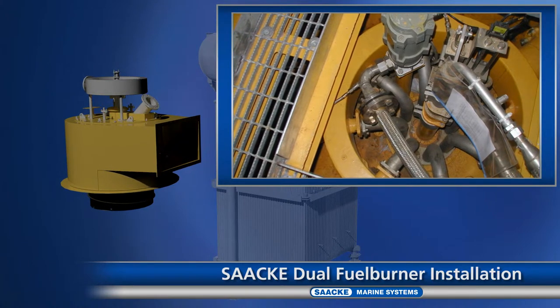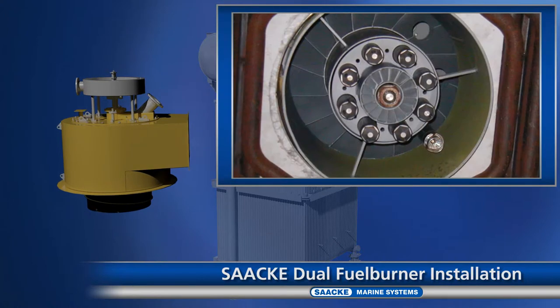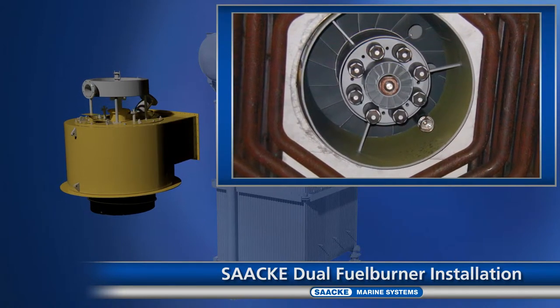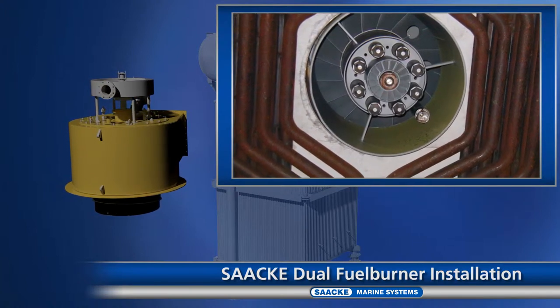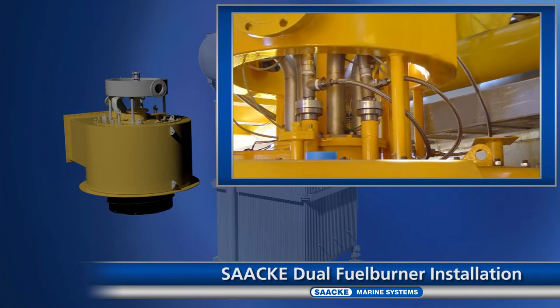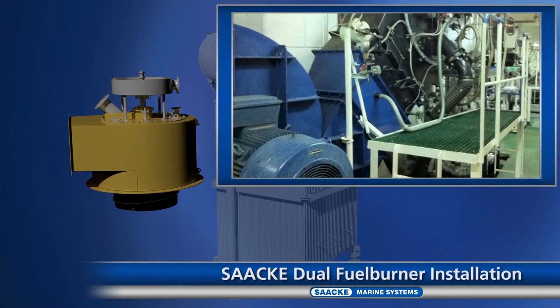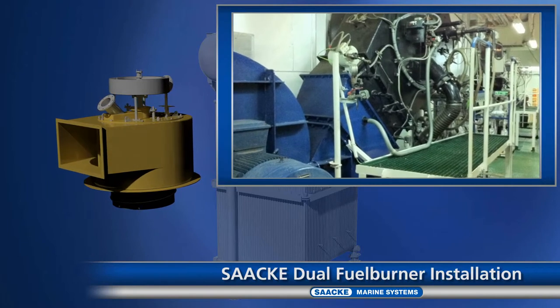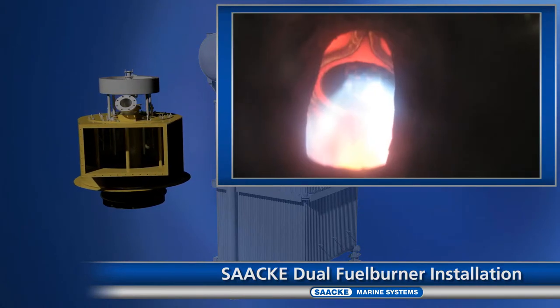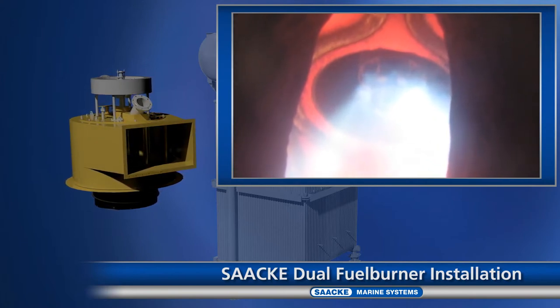All components match one another perfectly and are adapted to the flame shape. The range of products extends from inexpensive basic solutions to multifuel burners with several fuel lances for complex requirements, variants with explosion protection or air preheating up to 300 degrees Celsius. The innovative DDZG steam pressure atomizer sets emission standards and has a capacity range from 10 to 80 megawatts. Its biggest advantage is the flexible burner concept that permits simultaneous mixed firing of several gases also in combination with liquid fuels, such as crude or heavy fuel oil. Sensors indicate malfunctions immediately and provide for automatic changeover from one fuel to another. The DDZG burner with its low NOx flame and minimal maintenance requirements is optimally suited for use in FPSO applications and LNG carriers.